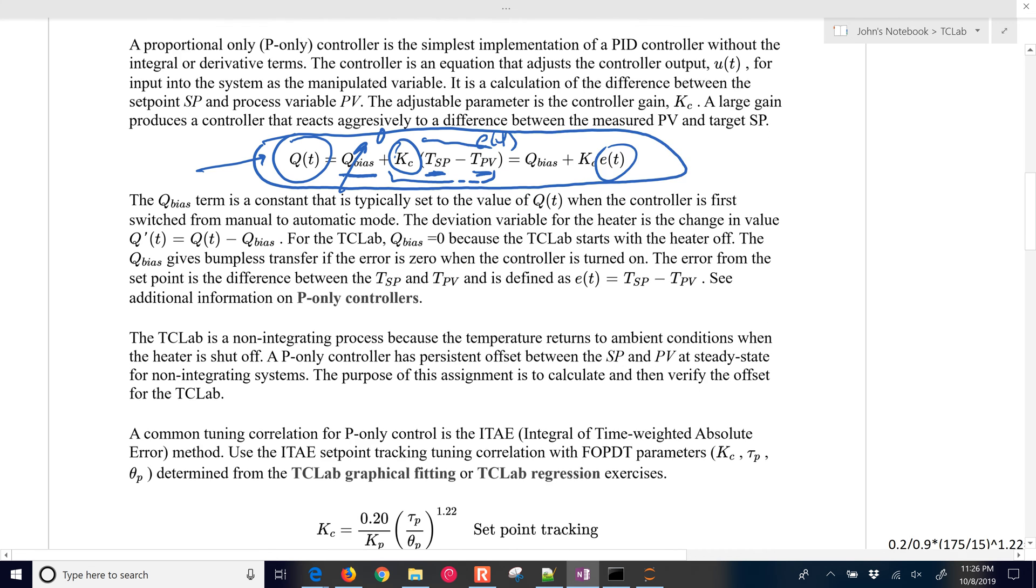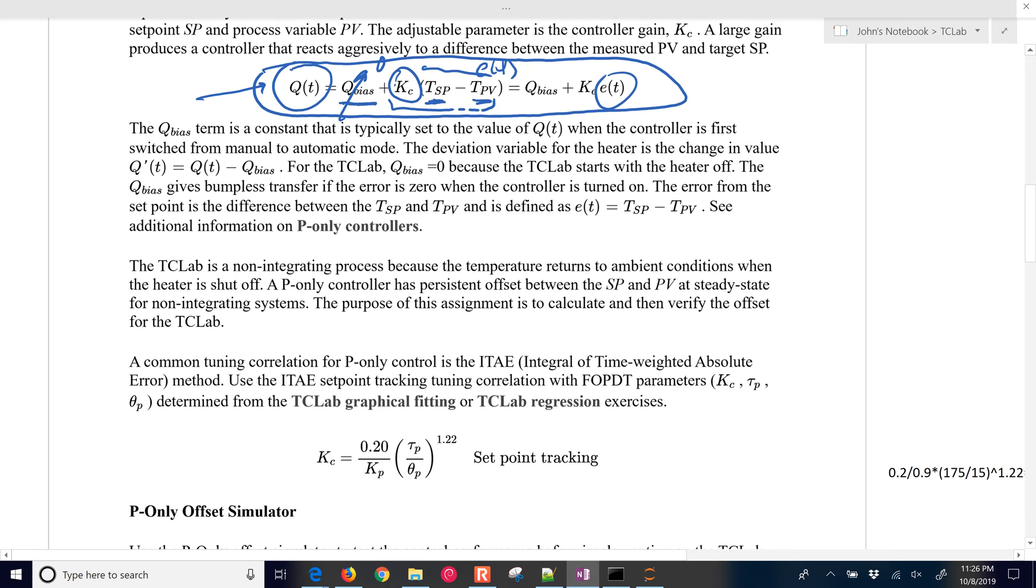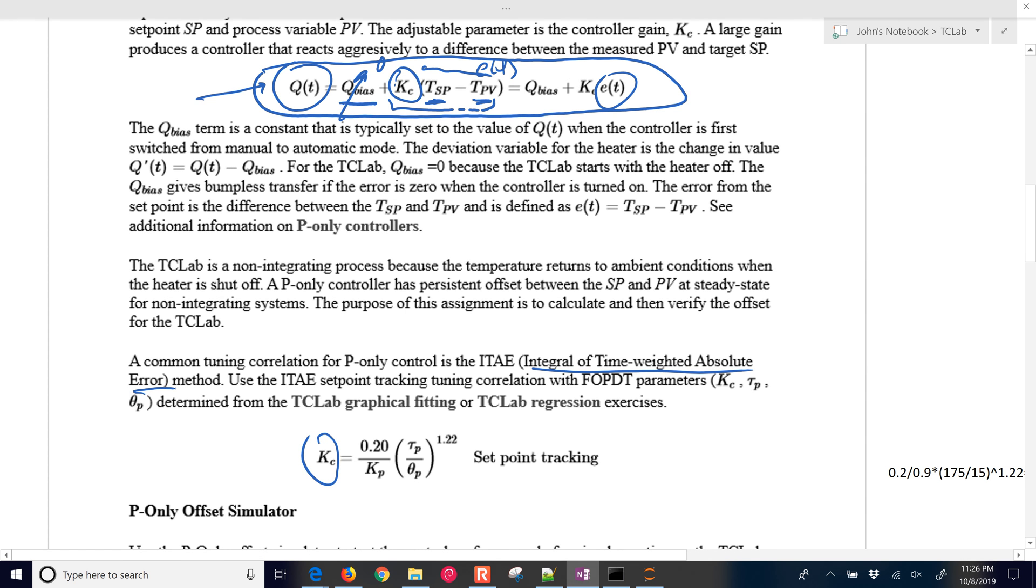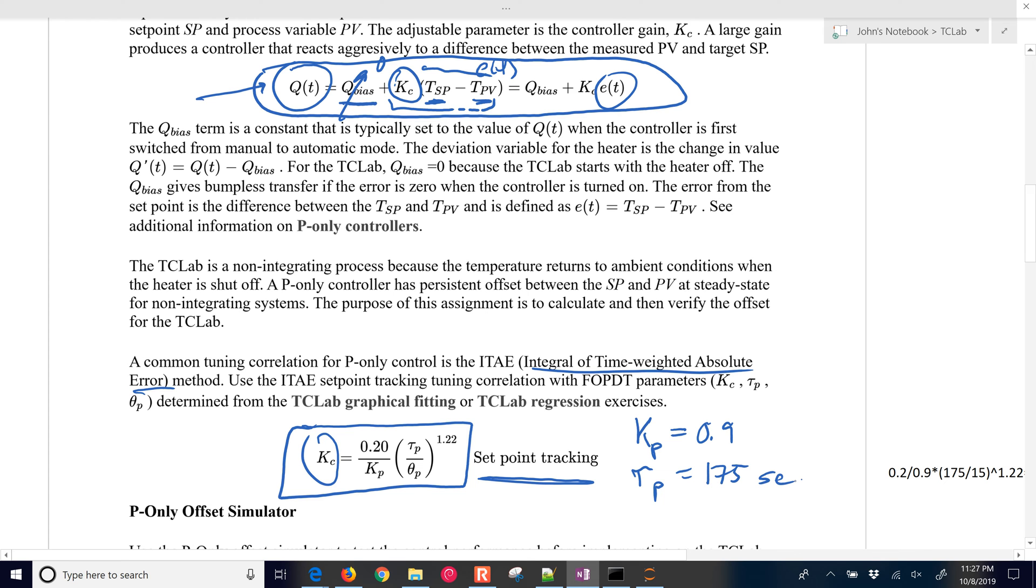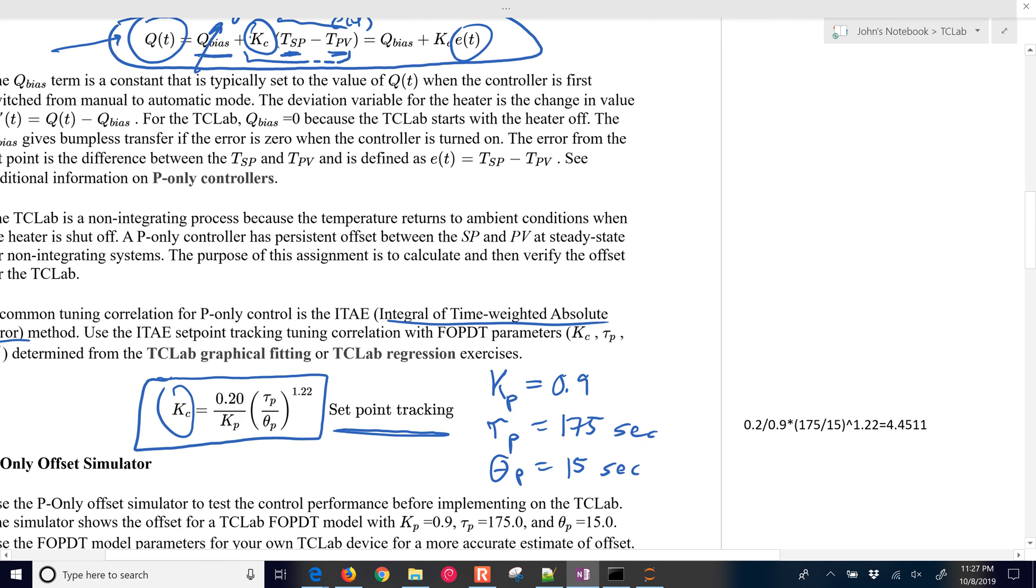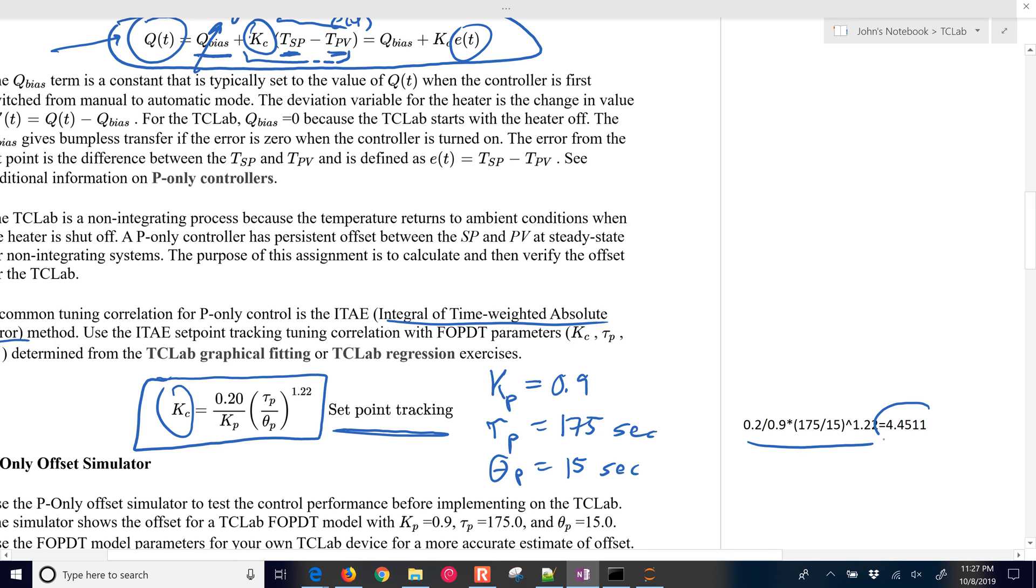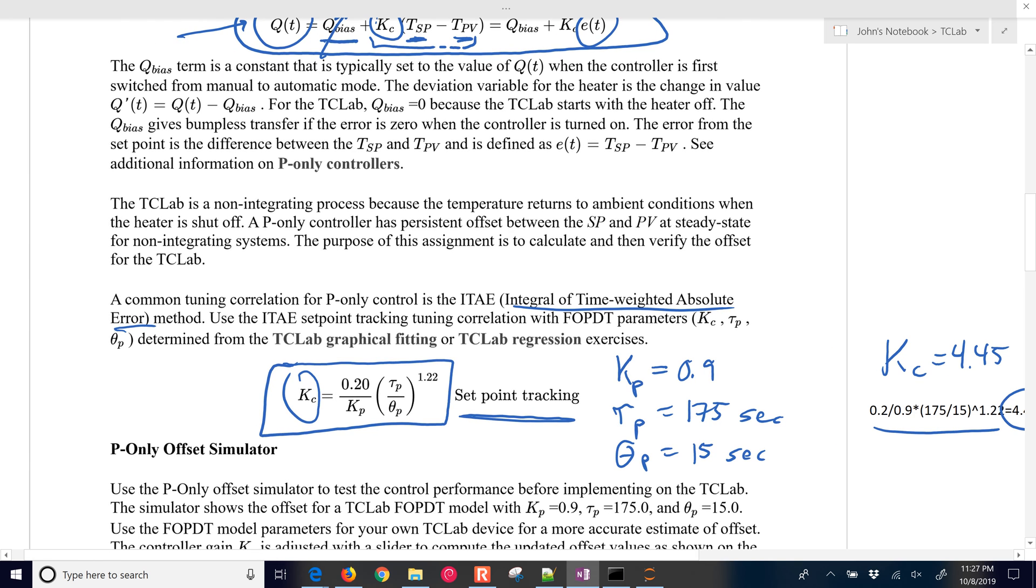So there's different ways of tuning to come up with good proportional controllers, to come up with the KC value. This is an ITAE, or integral of time-weighted absolute error method. And we're just going to use this one to come up with a good KC value for set point tracking. There's also a disturbance rejection mode. So in our prior studies, we came up with KP is 0.9, and tau P is 175 seconds, and then theta P was about 15 seconds. So if we calculate that, that is going to be 4.45 for our KC value. So that's the one that we're going to use.